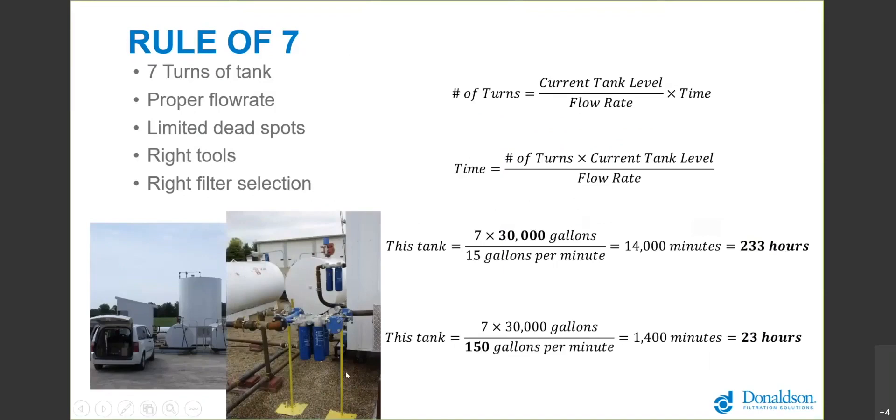In this application we applied clean, protect, polish. We filtered the diesel before it came on site through a single pass filter manifold that can handle the delivery flow rate. We applied trap breathers to the top of the tank and a dry air system, then filtered out any debris before it went into the equipment. It took a while to clean up these tanks, but once this solution is incorporated and your tanks are clean, these outlet filters don't plug very often.